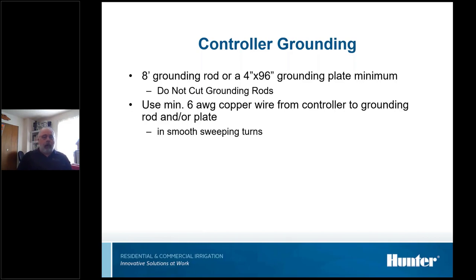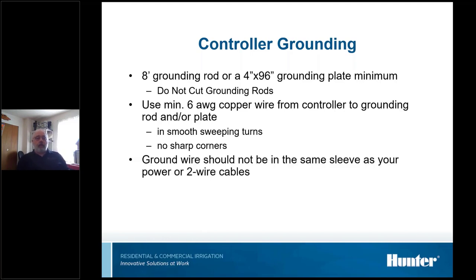One of the things with the actual ground wire, the 6-gauge wire, is that it needs to have nice, smooth, sweeping turns, no sharp corners. If you have a sharp corner on a ground wire like that, the surge is likely to jump off of the wire at that corner. So we want everything nice, smooth sweeps. We're trying to make it easier. You've probably all heard that electricity takes the path of least resistance, so a sharp corner is resistance. Also, on the controller, you never want to put the ground wire in the sleeve with anything else. It should be all by itself.